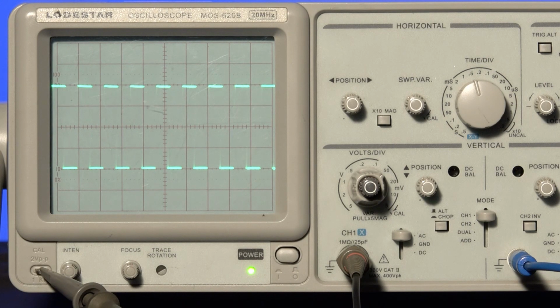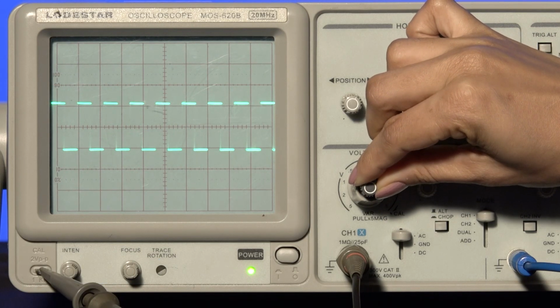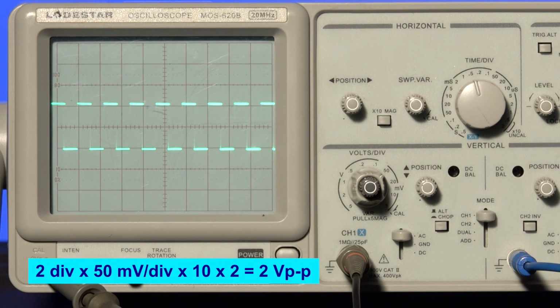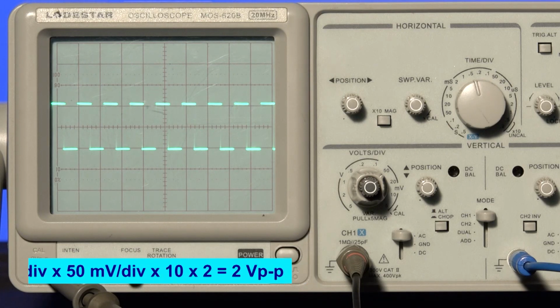As a solution, we can use the vertical variable knob to rescale the axis. Since we know the voltage level of the calibration signal, we can turn the knob until the waveform is displayed within a desired number of divisions. Let's bring it from 2 divisions to 1 division. That's 2 times reduction. With this new scale reduction, we must multiply the reading by 2. Now, the scales are all set.